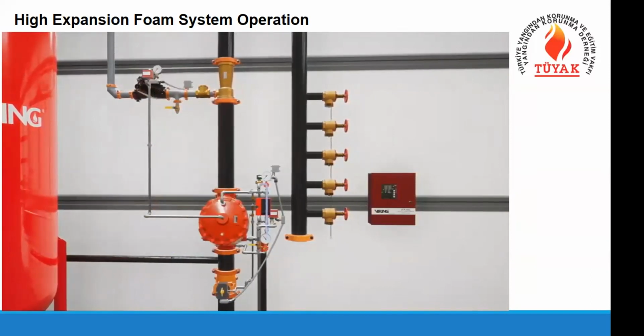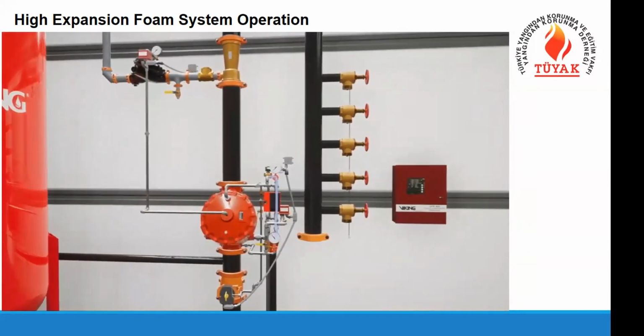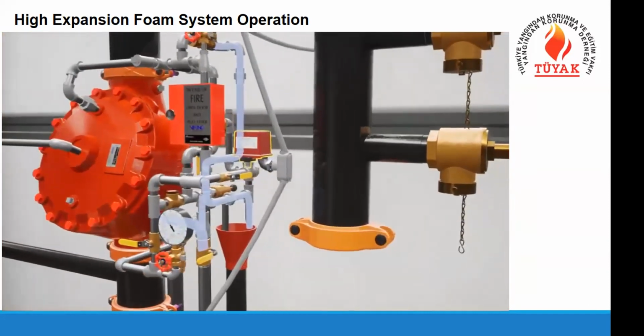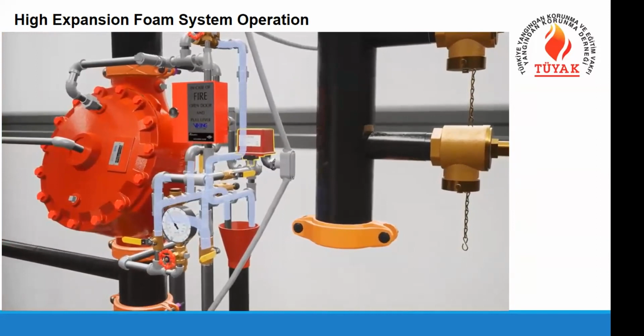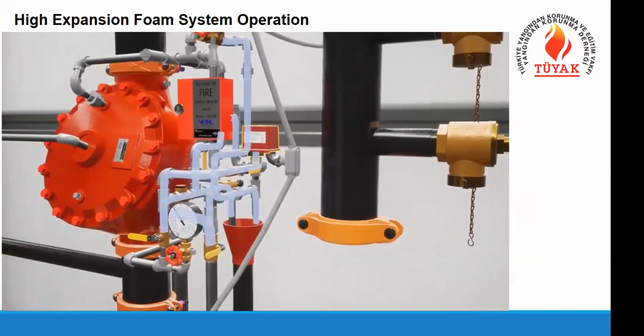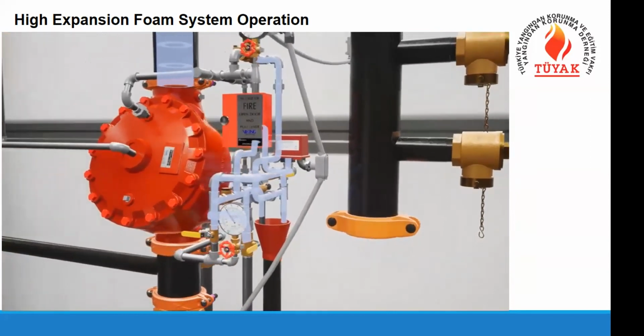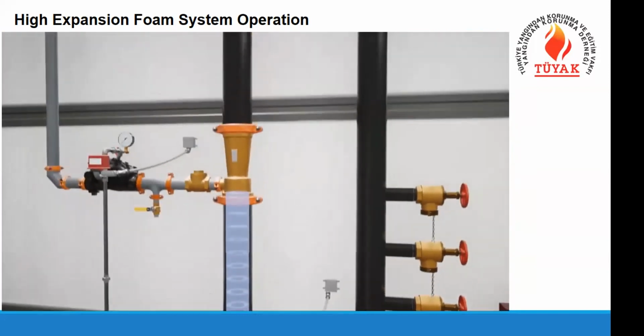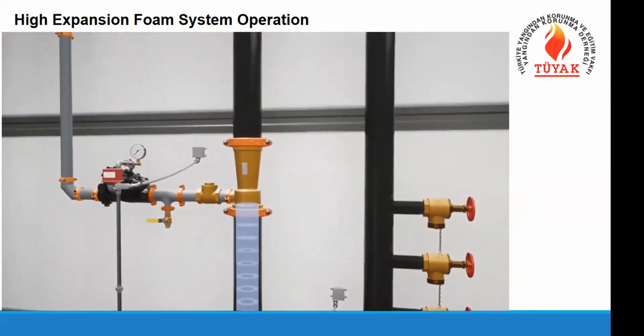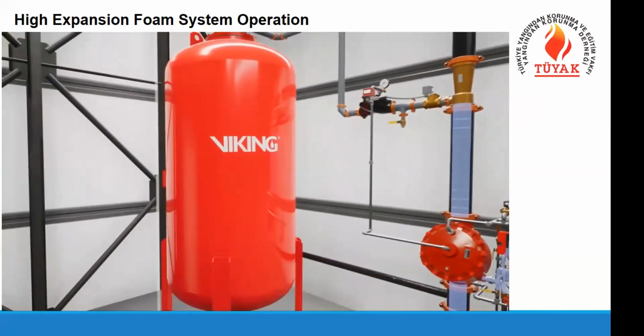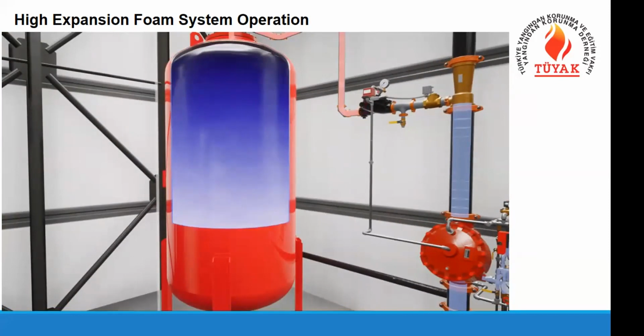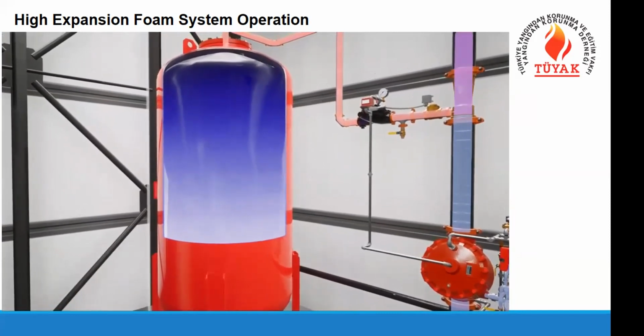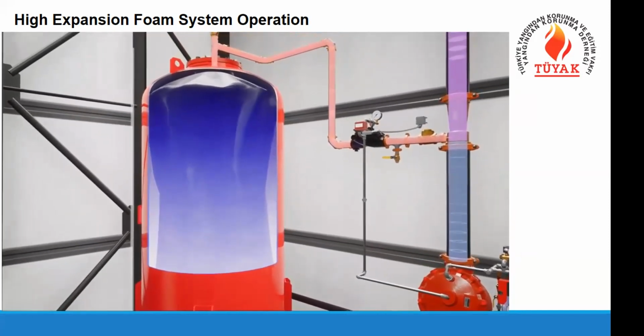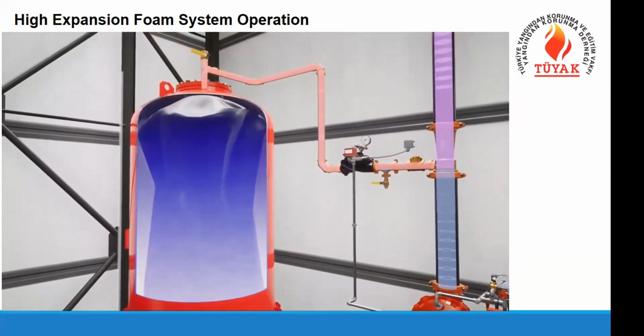While the next steps happen in parallel, we're going to look at the water side of the system first. Once the deluge valve is open, water will fill the trim and activate the water flow alarm. Water will enter the system riser, passing through the ratio controller. Occurring at the same time, on the concentrate supply, the foam concentrate is under pressure in the bladder tank. Priming pressure on the concentrate control valve drops, and the concentrate control valve opens. Foam concentrate begins to flow towards the ratio controller. The foam concentrate will pass through the metered orifice and then mix with the water into a foam solution.